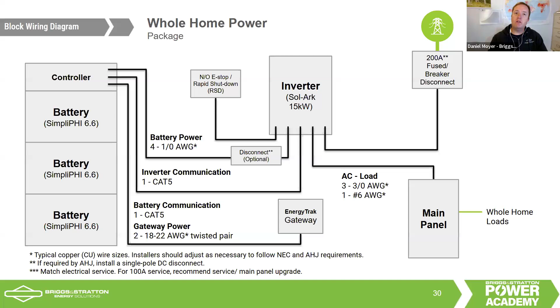By code, we need to have a rapid shutdown button located near the main service and the main disconnect, so that firefighters can hit that button. That tells the solar system that rapid shutdown has been initiated, and it will stop sending any power in and out of itself. It can also transmit up to the solar panels and activate the rapid shutdown modules at the module level on the solar. That's key, you want to make sure you install that.